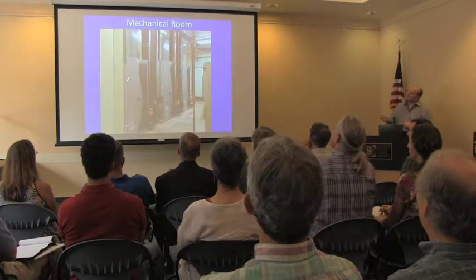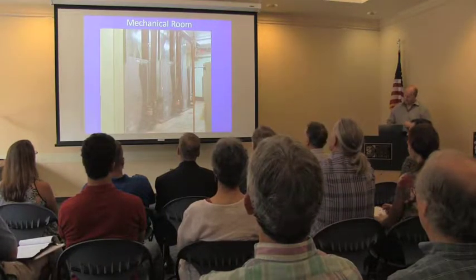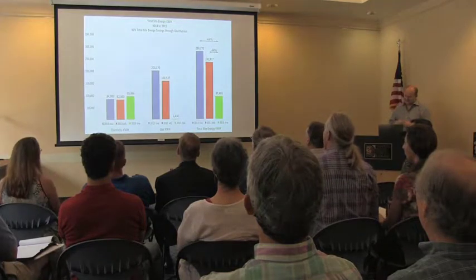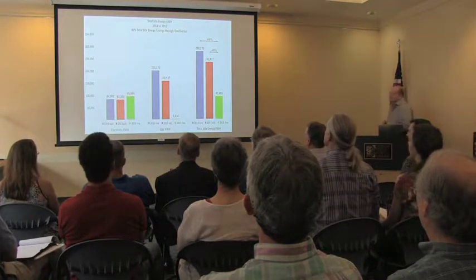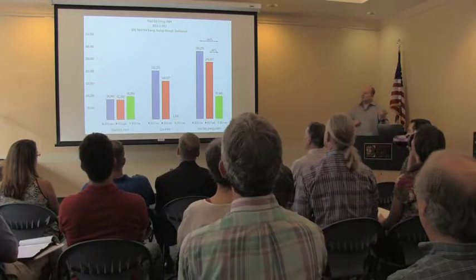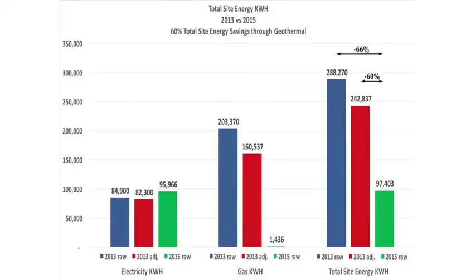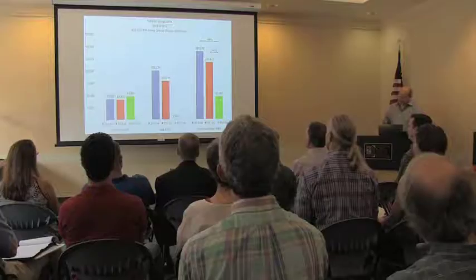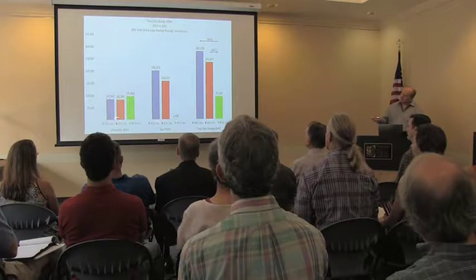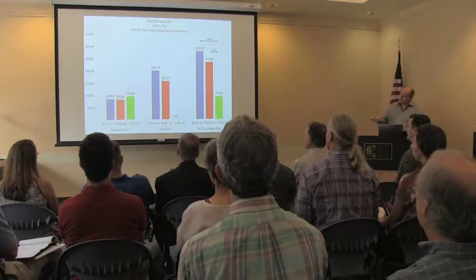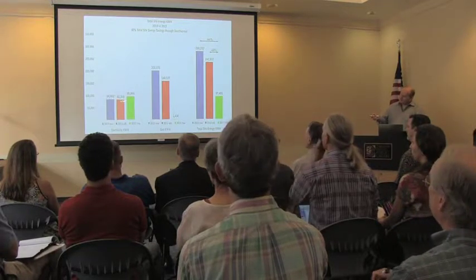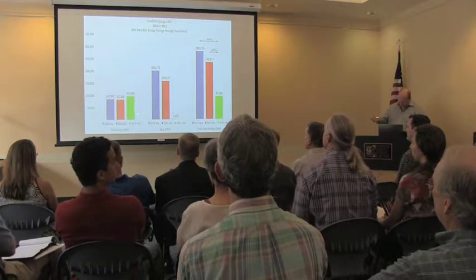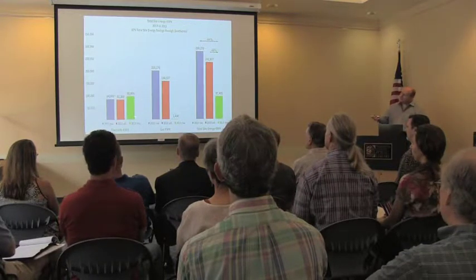Mechanical room, you can see three heat pumps there. They have a total of five there. And here was the energy impact of the whole site. So what we did is we measured the energy use in kilowatt hours of the geosystem as well as the heating system. So this was the electricity usage in 2013. And this was 2015 after it was converted.